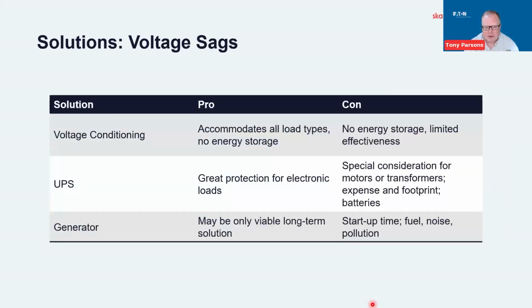With each of these solutions, there are pros and cons, and we're not going to go through and dwell on every single thing here, but just the idea, for example, the UPS is great for protection of electronic loads. What are some of the drawbacks? If you're feeding loads that draw inrush current, like motors or transformers, they may have some limitations. You may have to upsize them significantly, which increases the expense and potentially increases the footprint. And then maybe you have to deal with batteries that you didn't have in your system before. So again, footprint for that, but also potentially introducing additional hazards that you didn't have to worry about before you had those in the system.